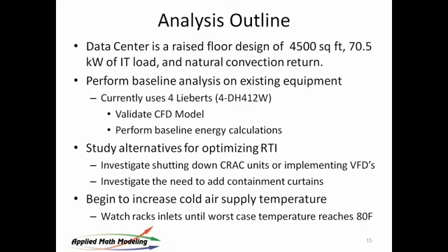But this is a very typical data center, and this is a real live data center, a colo that agreed to allow me to use their data center for analysis purposes here today. 4,500 square feet. Now, this is also very typical, is what they often do is build it for worst case analysis. I believe these are 30-ton units roughly, 30-ton CRACs. So they've built this thing for, and the kilowatts there is really 412. So they've built this thing for 1.6 megawatts of total load, and they're running it at 70. We see this a lot, don't we?